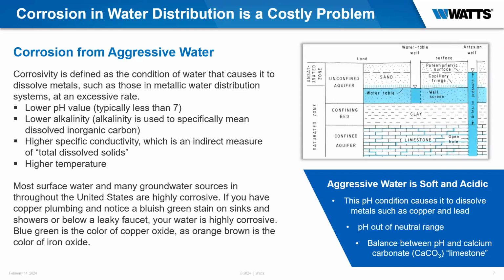No problem. So we're going to talk a little bit about corrosion to help you understand it. Corrosion from aggressive water usually has a low pH value and more total dissolved solids. The big thing is with the lower pH condition, it actually dissolves metals, such as copper and lead.